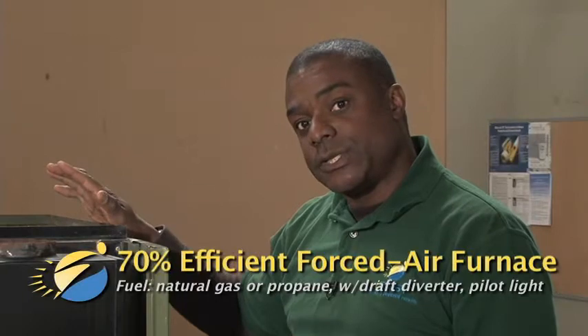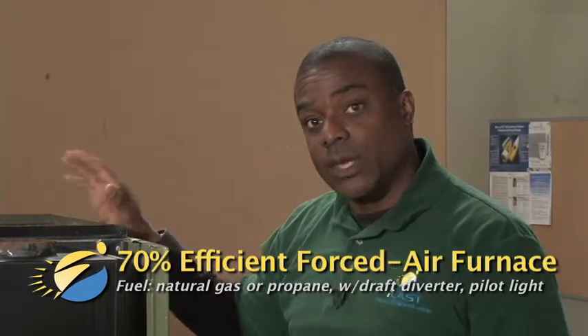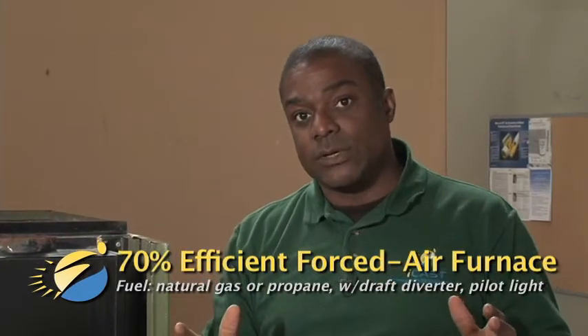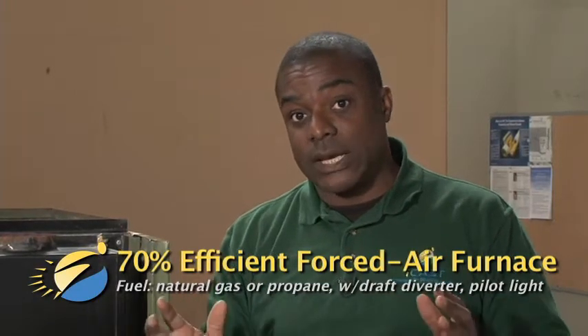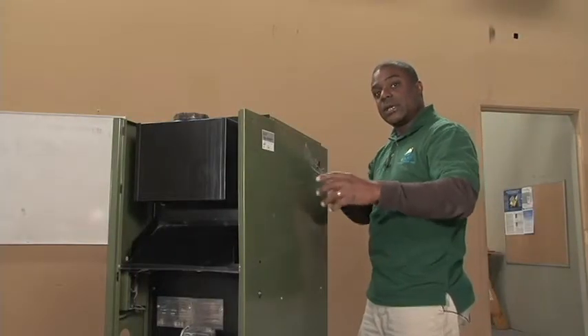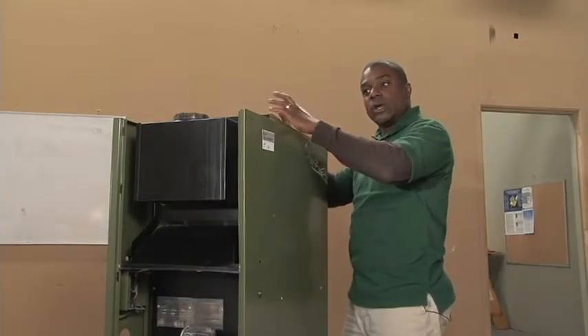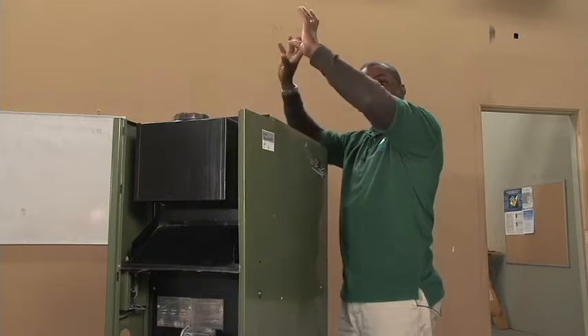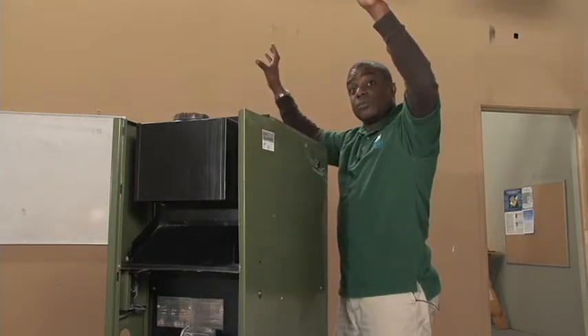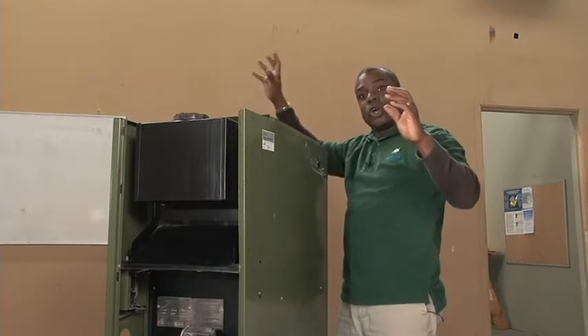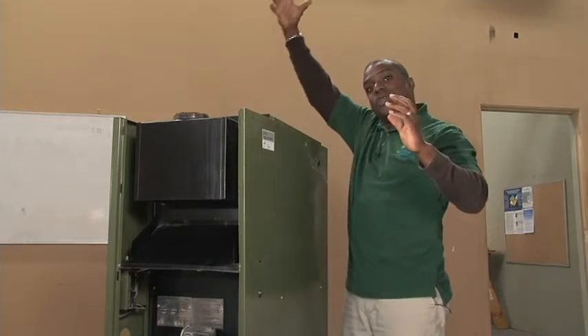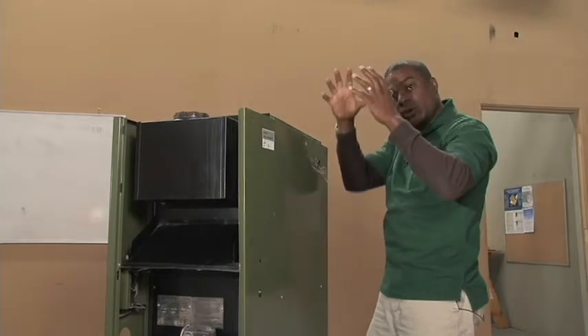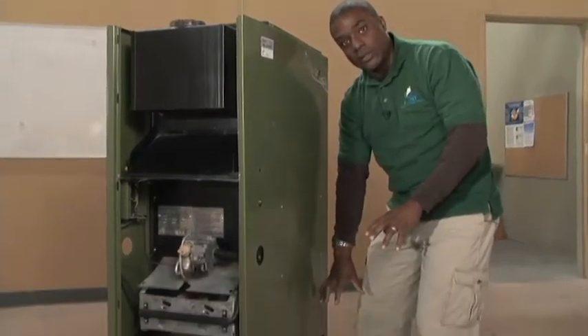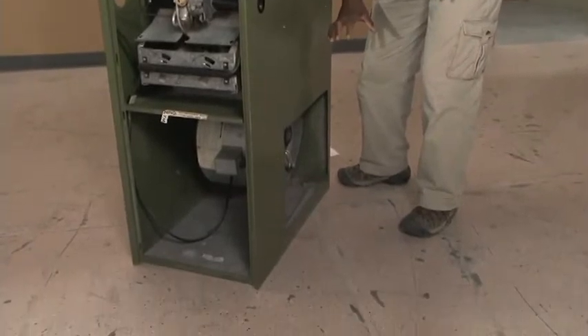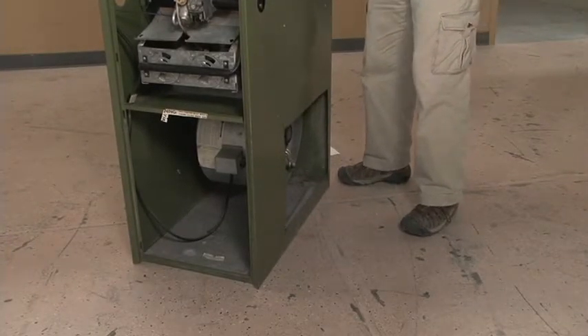This is a 70% efficient forced air furnace. Now we'll remember from our HVAC unit that a forced air system has two sides. It has a supply side and a return side. Our cycle begins at the top of our furnace where it supplies hot air to the rest of the house through our supply ductwork. Then cold air from the house returns through return ductwork to the bottom of our furnace where it gets sucked in by the blower and the whole cycle begins again.